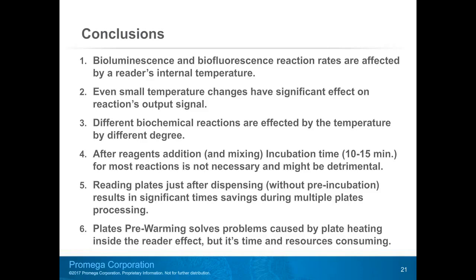is not necessary and might be detrimental. Reading plates just after dispensing without the pre-incubation results in significant time savings during multi-plate processing. Pre-warming plates solves the problem caused by the plate heating inside the reader, but it also consumes time and resources. Thank you for your attention.